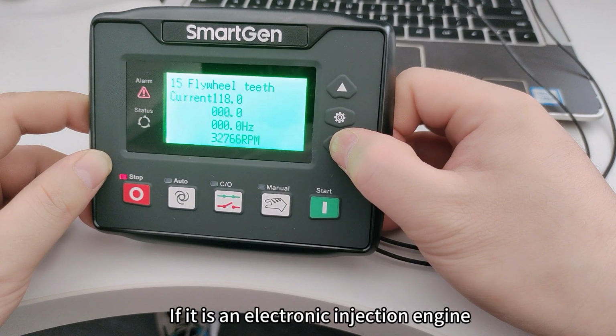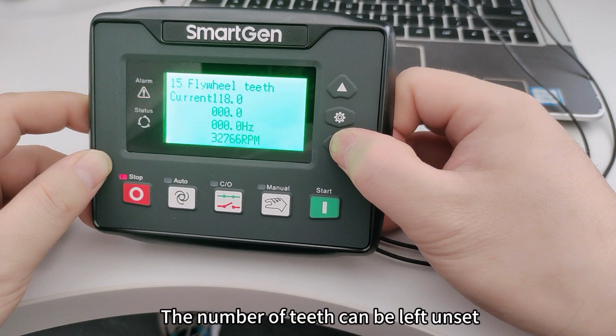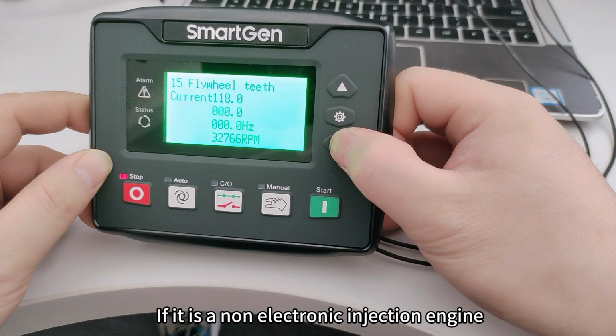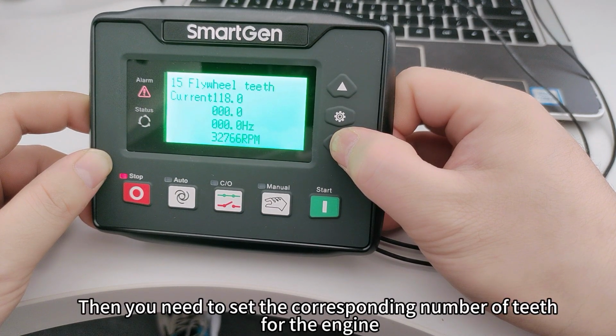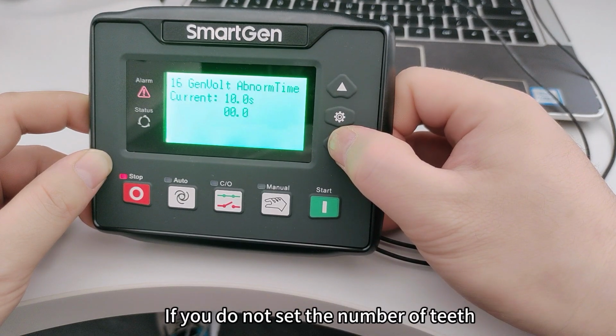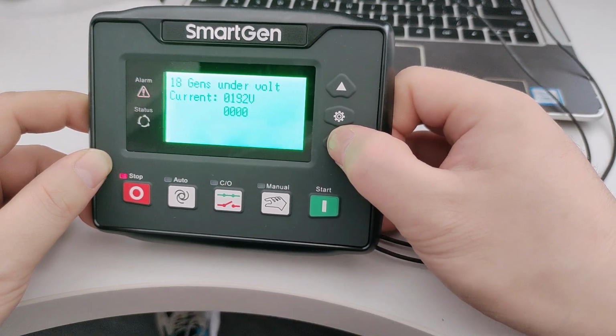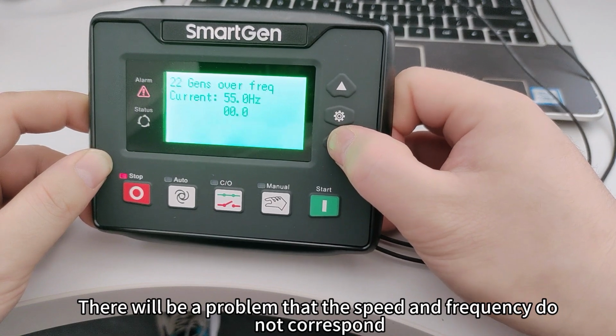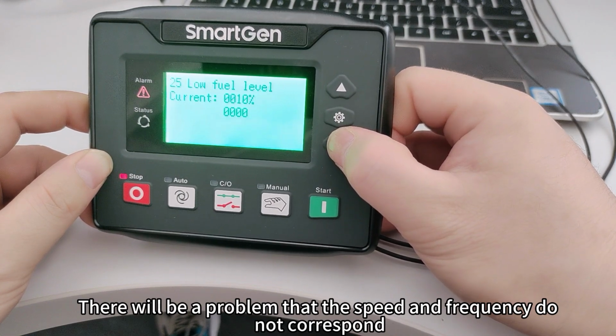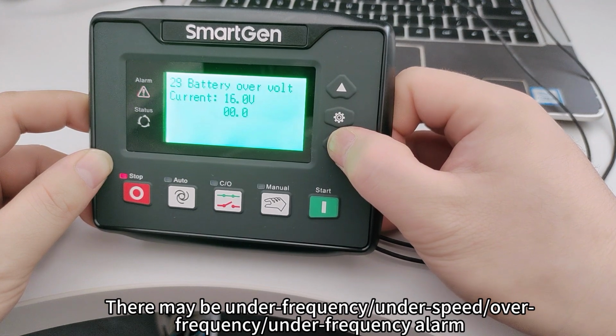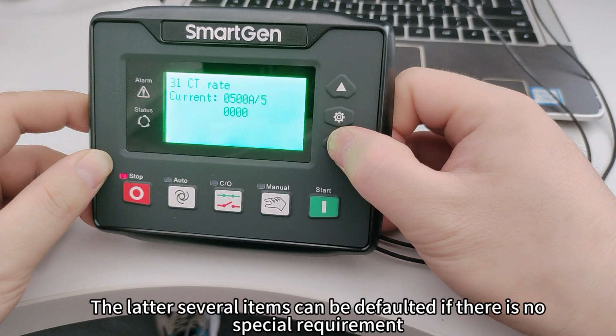If it is an electronic injection engine, the number of teeth can be left unset. If it is a non-electronic injection engine, then you need to set the corresponding number of teeth for the engine. If you do not set the number of teeth, there will be a problem that the speed and frequency do not correspond. There may be under frequency, under speed, over frequency, or over speed alarms. The latter several items can be left at default if there is no special requirement.